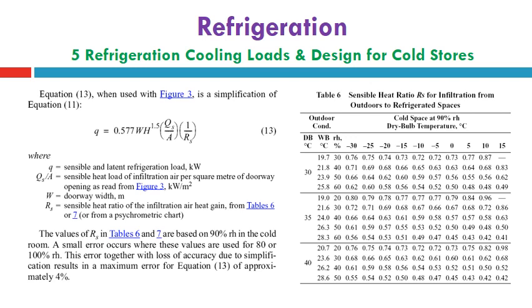So it should be clear that this equation is a simplified equation rather than the equation listed in the previous slide, equation number 11. The values of RS in table 6 and table 7 are based on 90% relative humidity in the cold room. A small error occurs where these values are used for 80 or 100% relative humidity. This error, together with loss of accuracy due to simplification, results in a maximum error of equation 13 of approximately 4% regarding the base equation, which is numbered here in this lecture and chapter 12 as equation number 11, which has been generated since 1975 by Dr. Hani Ulama.